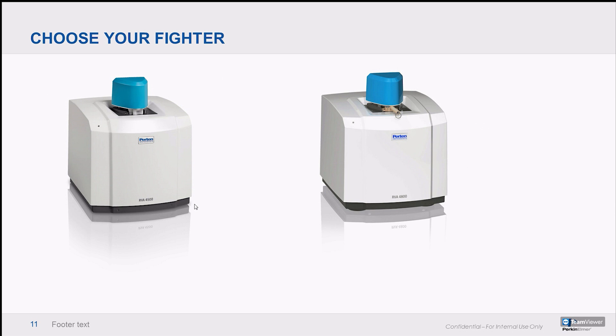It's the job of product development and quality groups to strike a balance between the expansion conferred by amylopectin and the film-forming crisp properties — controlling waxiness and viscosity behavior of incoming ingredients really impacts final product performance. This is where the RVA comes in. The RVA 4500 has been the industry standard for a long time, and now the RVA 4800 has enhanced capabilities, going up to 140 degrees C — entering the range of temperatures actually present in an extruder barrel. For heat-resistant starches or proteins, this allows observation of ingredients under those real conditions.